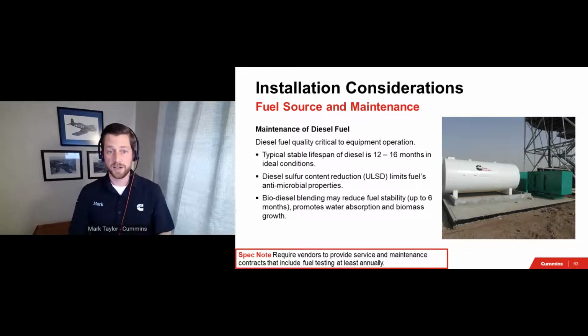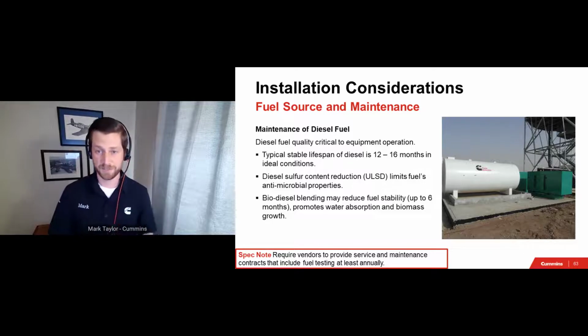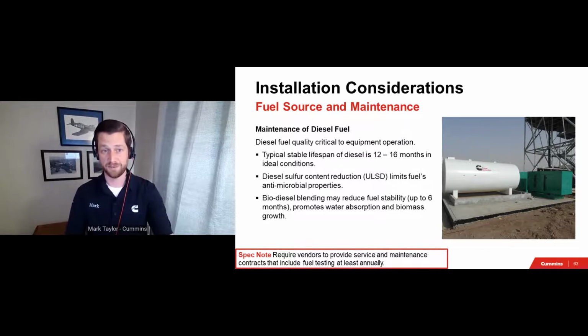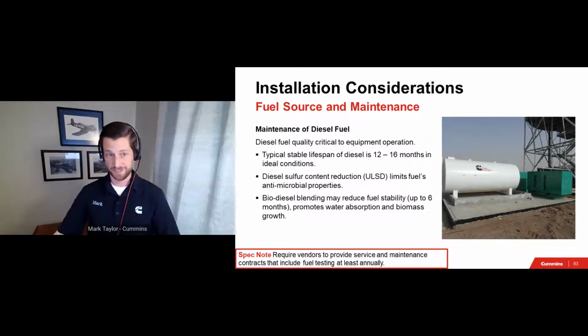So the key takeaway here is to not assume that on-site stores of diesel fuel will stay perfect forever. NFPA 110 calls for annual testing of the fuel. And if the fuel is of substandard quality, it needs to be polished or potentially replaced. Another key tip, don't put off getting that service started. Establishing an early baseline result during commissioning is the best point of comparison for future test results.